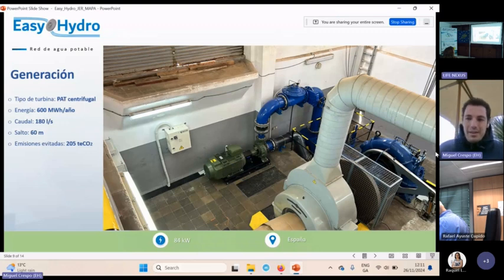Another case study is on old hydropower plants. So this is in Spain, in an old hydropower plant that uses a water tank installed 67 meters uphill. But the case here is that the old Francis turbine that you can see on the right of the slide was stopped for the last 5 years. So basically, they were not generating any energy at this hydropower plant. So the operator just contacted us to make a proposal and a design.